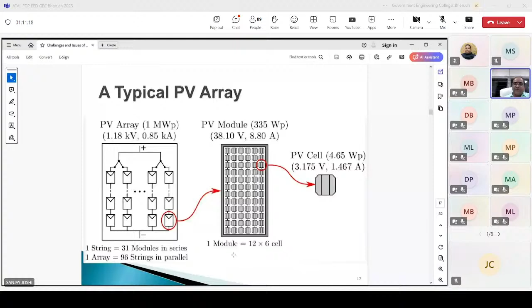Now let's turn our focus to the PV array. This PV array has a peak power rating of 1 megawatt, voltage rating of 1.18 kV, and current rating of 0.85 kiloampere, or 850 ampere. One array consists of 96 strings in parallel, and in one string, 31 modules are connected in series. This is a typical arrangement of a typical PV array.